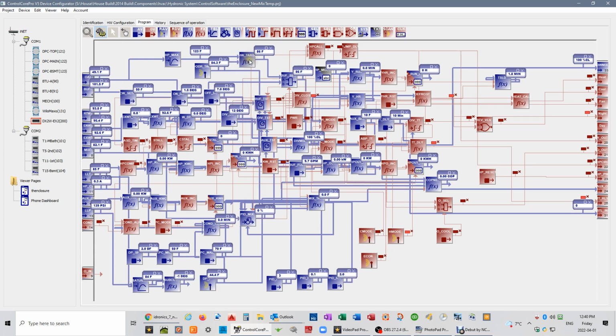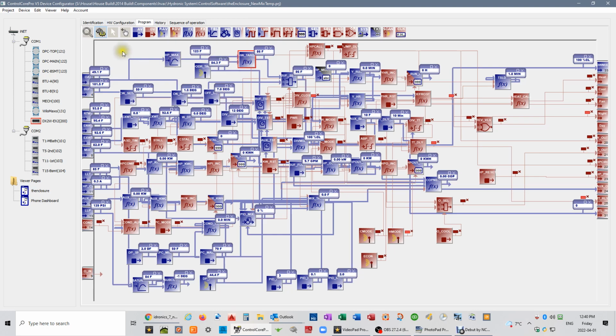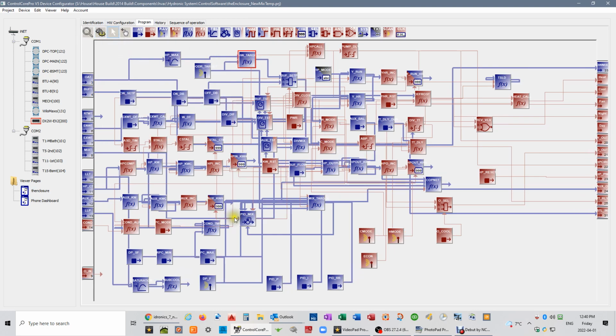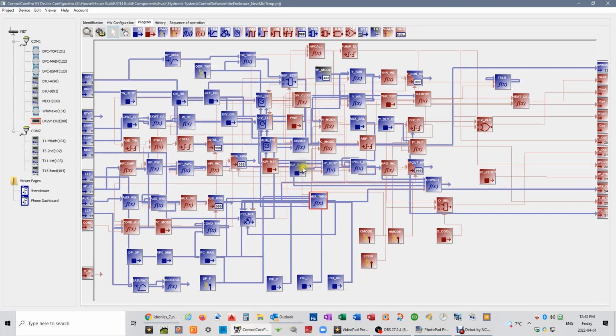But when we get to our target, I need to find where that's for hot water. Hot water target, where is the cold water target? I'm going to turn the program off so that I can see the names of the actual things. And I think I'm going to have to throw in the towel on how it's creating this. I haven't analyzed the cooling side of the system yet. I know part of it is the mixed temperature. So we have cooling mode times something. This is where cooling mode is. So if it was set to cooling mode, this would be true, therefore it would be 1. And therefore, it's 1 times something as opposed to 0 times something. Obviously, if it's 0, all of this would be false. But it's got min, max, dew point F, which is, I think, an SF. I'm not sure what Benoit has done for that.